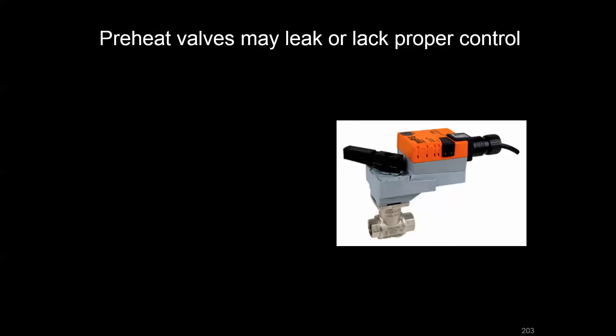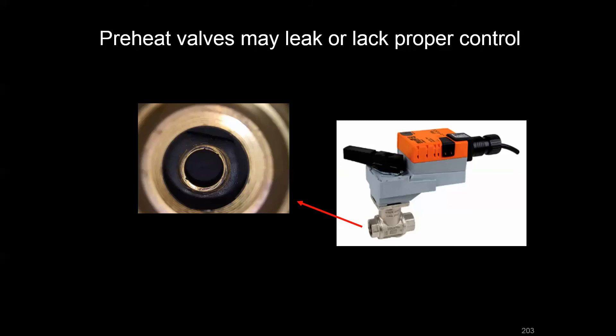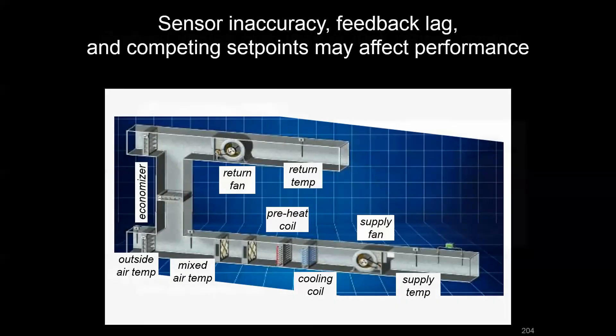Even with control logic to prevent preheat and cooling coils from fighting each other, a preheat valve with internal pits and grooves can allow a small amount of hot water through even at zero percent command. That hot water into the coil becomes a load the cooling coil must now pick up. There are also many other set point coordination and tight control loop requirements throughout the system.